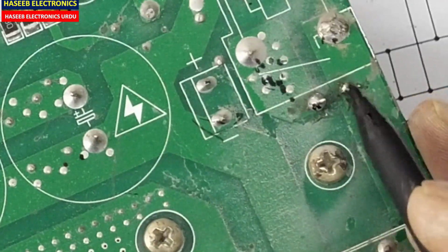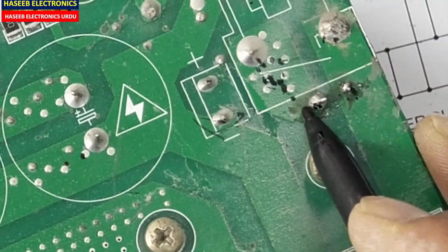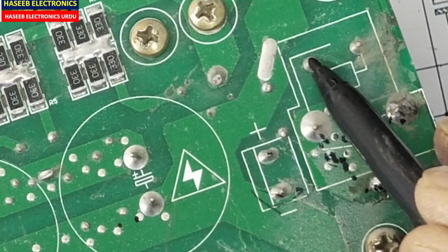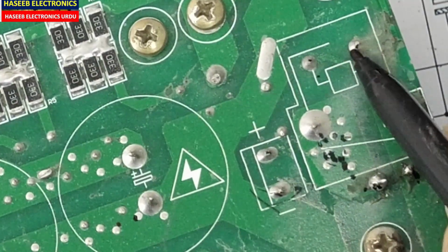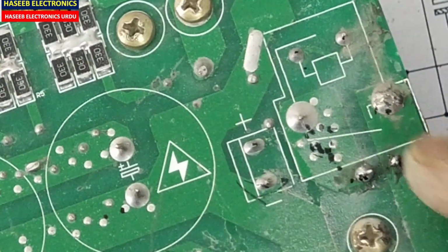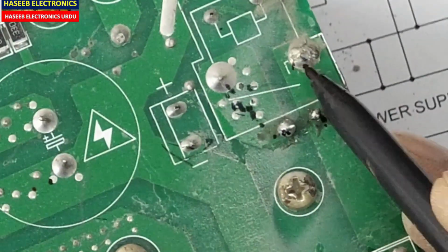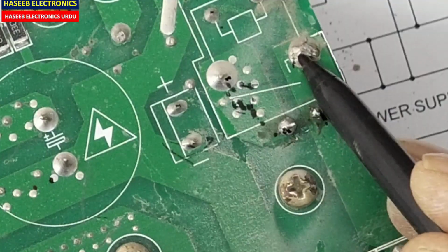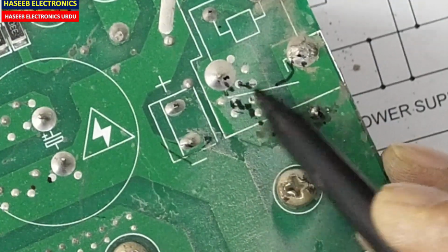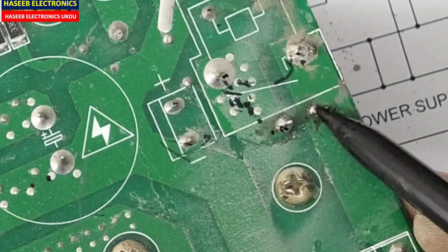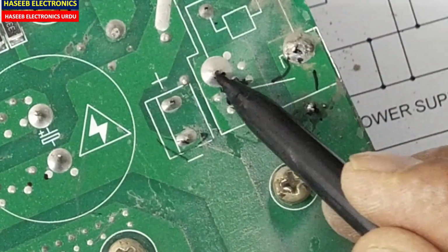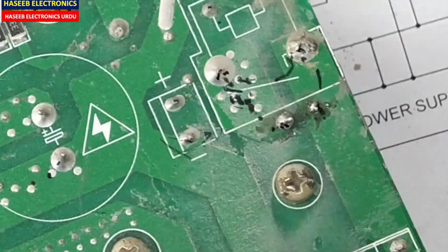Initially the current will pass through this component. When the low voltage power supply is turned on and we have 24 volt here, this relay will turn on and close its two internal contacts, so it will make a jumper from here to here. The current, first passing through this component, will now pass through this arm and reach the capacitor.